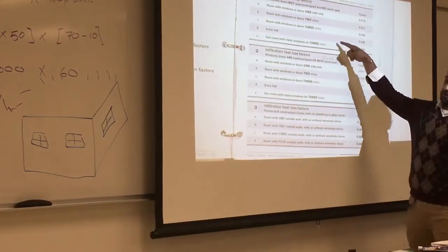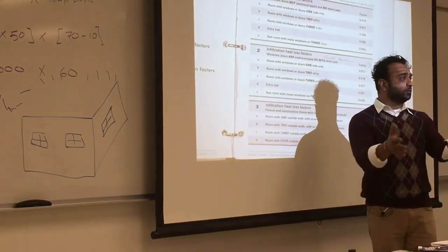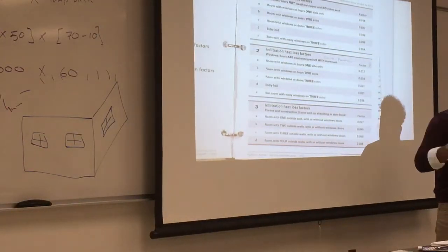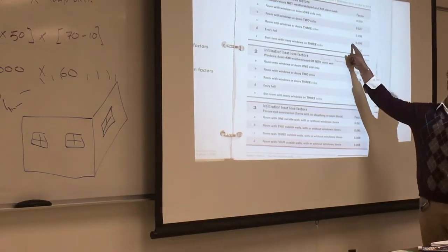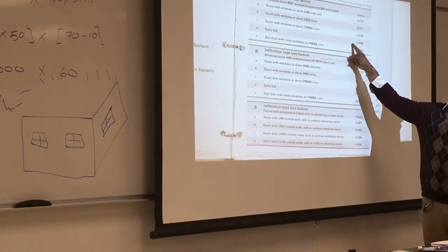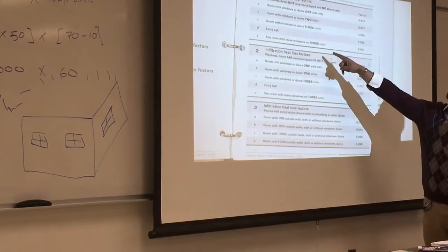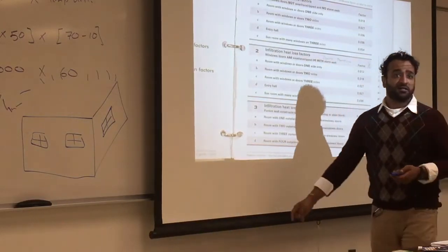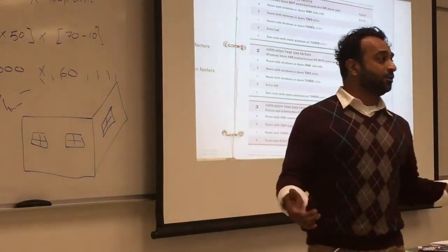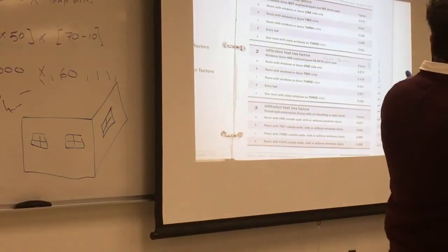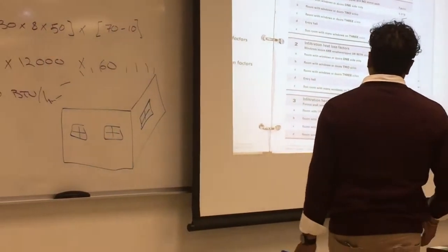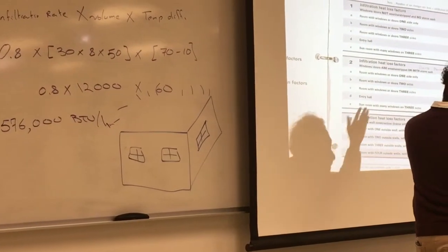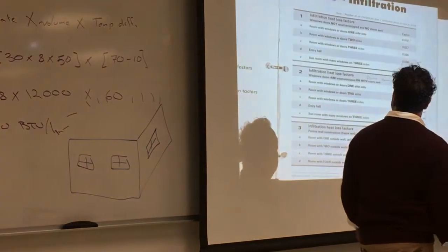2 sides. You can have 3 sides as well. Sometimes the room will be sticking out. Or have 3 rooms and 3 sides, you can use 3 sides. Entry hall, you have a door coming into the house, you can use this factor. Sunroom, with many windows on 3 sides. Sunrooms are very popular. You go in a sunroom, it's all windows, so you can use a big factor. Again, these are very general rules, came from construction and repetition, so we'll stick with those numbers.